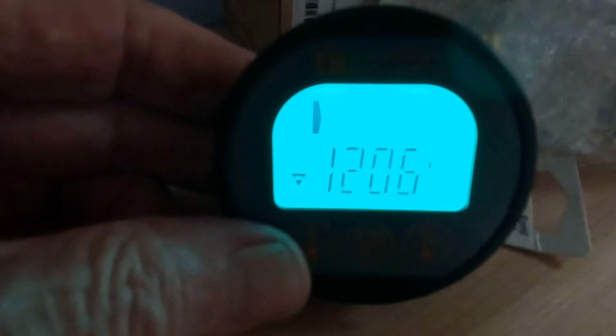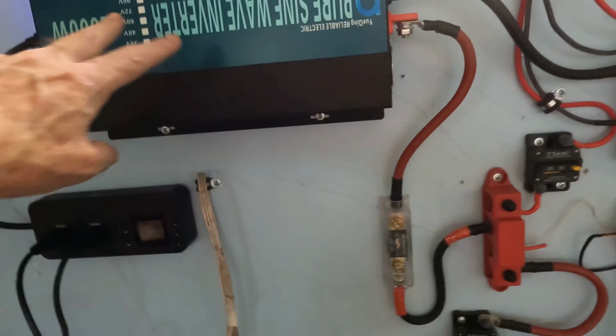Just for fun, I'll show you a comparison. It's reading on the shunt 12.06 volts. On the battery display, 12.5 and 75% full. Nope. Let's go to the Victron app, which is pretty accurate usually, and it's reading 12.02 volts. So the Victron app and the shunt are very close. I'm looking at the shunt right now, it's 12.05, and the Victron's reading at 12.02, so very close there. I just looked at my inverter in the front here, and it was reading 11.8, so a little discrepancy.